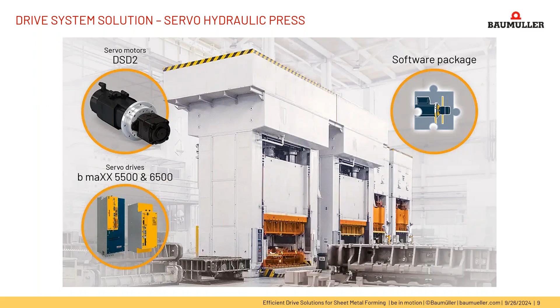Baumüller servo drives can be equipped with integral pressure controls for pumps with constant displacement volume. This function is available in our BMAX 4000, 5000, and 6000 series drives. Only 2 set points, pressure and volume, are required and can be sent via analog or over the fieldbus. The actual pressure feedback from a pressure transducer is read directly by the drive's analog input and makes this system very responsive.